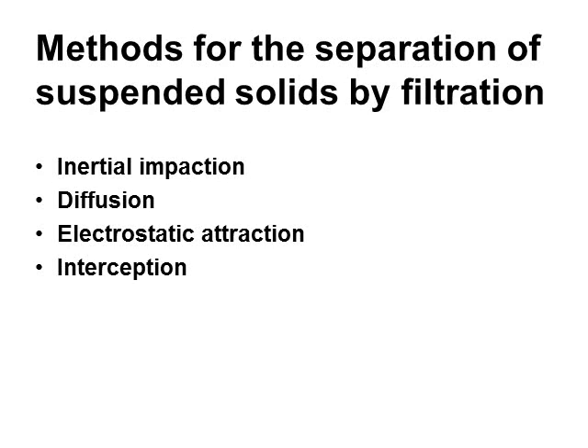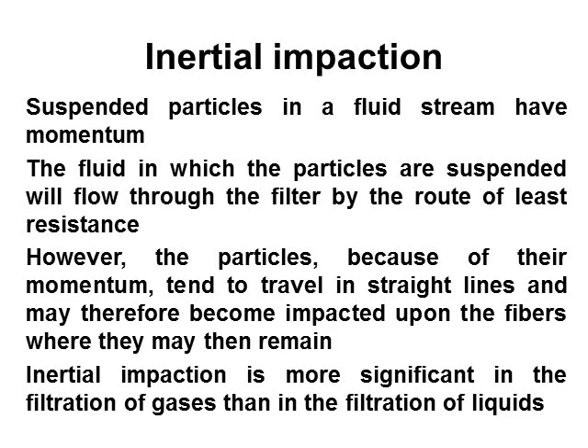Methods of suspended solids separation from a fluid during filtration include: inertial impaction, diffusion, electrostatic attraction, and interception. In inertial impaction, suspended particles in a fluid stream have momentum. The fluid flows through the filter by the route of least resistance; however, the particles, because of their momentum, tend to travel in straight lines and may therefore become impacted upon the fibers, where they may then remain. Inertial impaction is more significant in the filtration of gases than in the filtration of liquids.